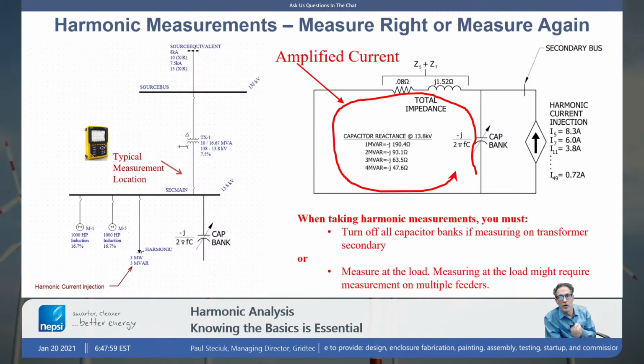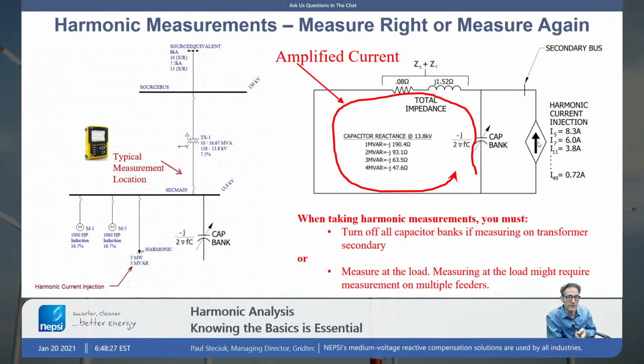utility. Oftentimes we have customers, existing plants, where they're trying to evaluate: does the plant comply with IEEE 519, or the harmonic distortion limits as dictated by the utility? And they will send a measurements person out to take some measurements. Oftentimes they're trying to take measurements because they want to get the current injection here for their model. They want to create this model. So they're trying to figure out, well, what is my current injection? They take measurements and they leave this capacitor bank on. Okay, that's a mistake.